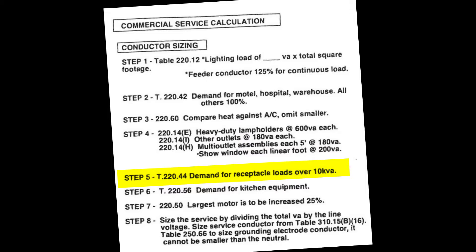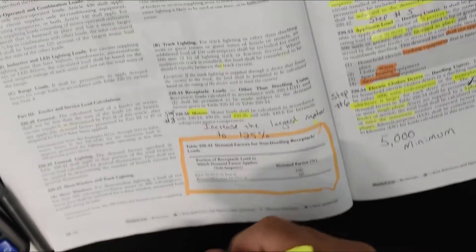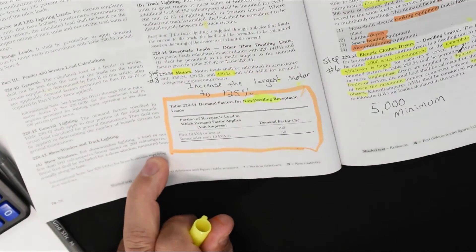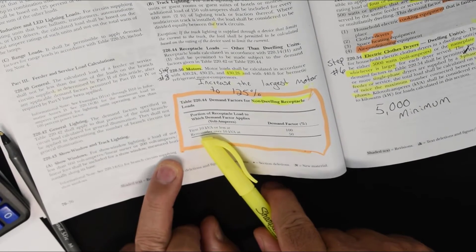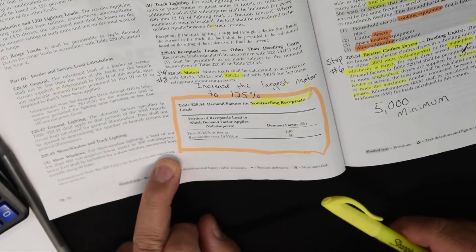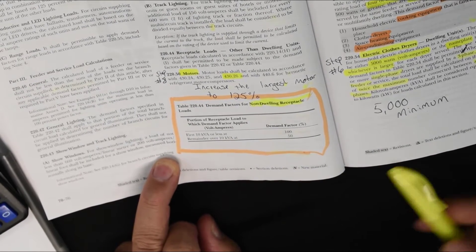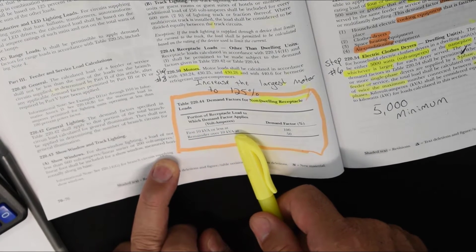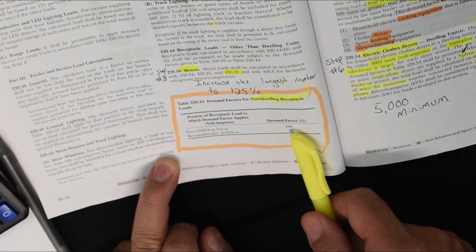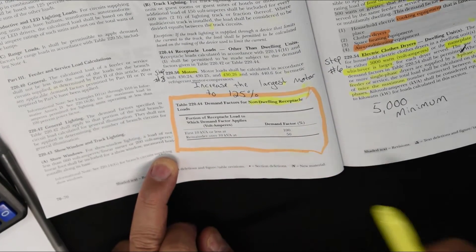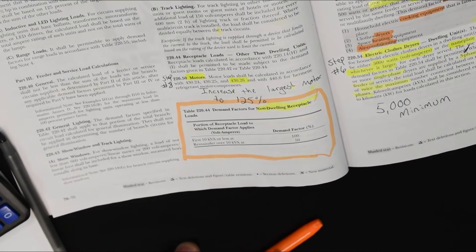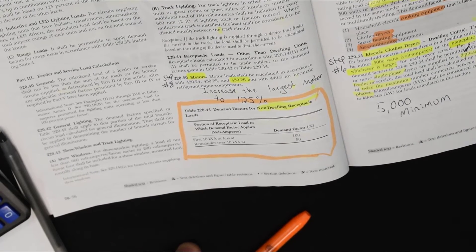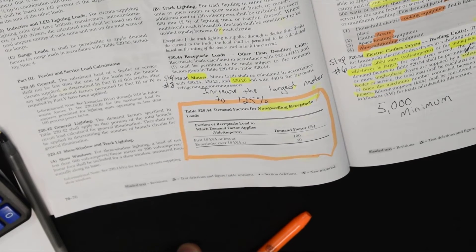Step 5 takes us to Table 220.44, demand for receptacle loads over 10 KVA, which is specific to non-dwelling occupancies. After adding up all your receptacle loads at 180 VA each, or 1 VA times square footage, the first 10,000 VA or less is at 100%, and anything over 10,000 VA is at 50%. This reduction reflects the reality that a receptacle has no load by itself — only whatever is plugged in — so not every receptacle will be used at full capacity all day long.